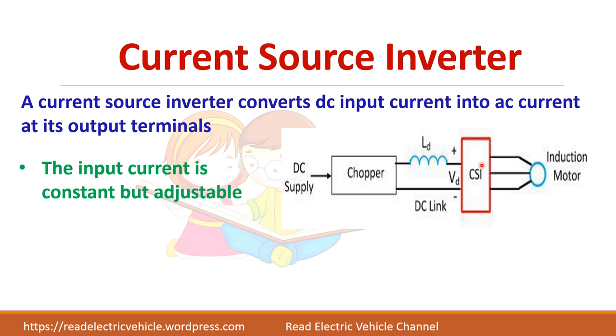This is a current source inverter feeding an induction motor. This is a chopper. If you have a DC supply you can use a chopper directly, or if you have an AC supply you have to use a diode bridge rectifier along with the chopper. The output of the chopper is a controlled DC voltage connected in series with a high value of inductance, the combination of which acts as a constant current source.